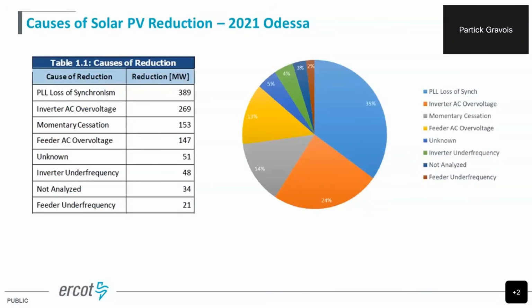We did a lot of root cause analysis. We sent out RFIs to all the facilities asking why the inverters tripped. We got all those responses. We went through them, and most had fault codes that said why the inverter tripped. We did a lot of follow-up work with NERC and Texas RE to reach out to these facilities and do more root cause analysis. And all of this went into the NERC report that was released as well. So this is the breakdown of the major causes of reduction that we saw.